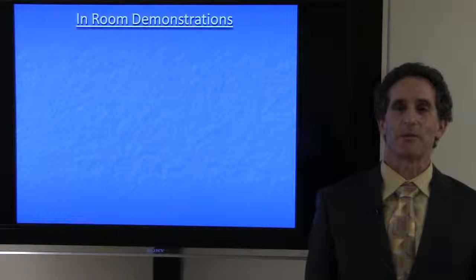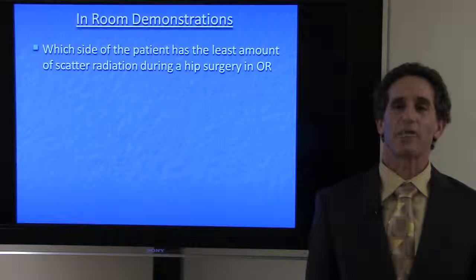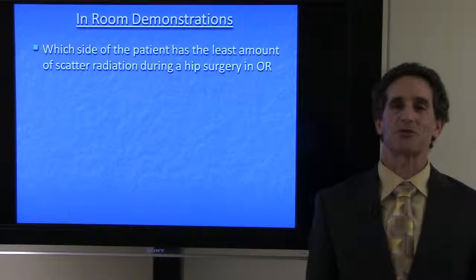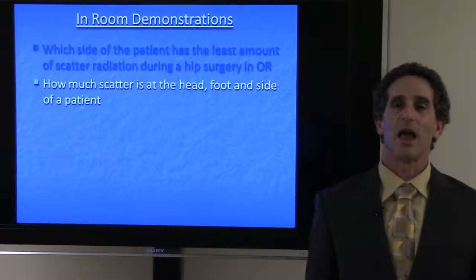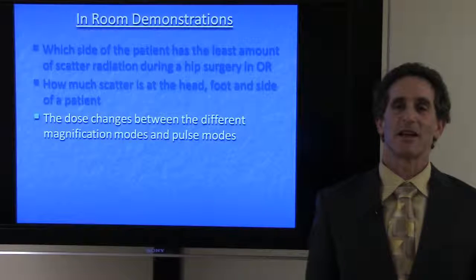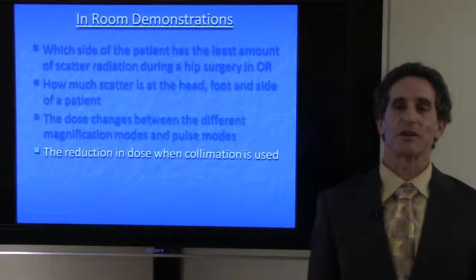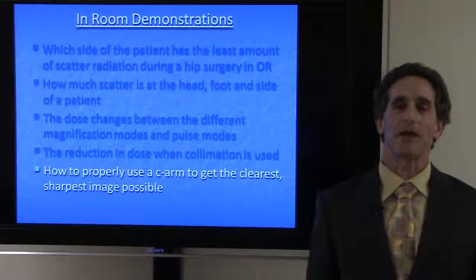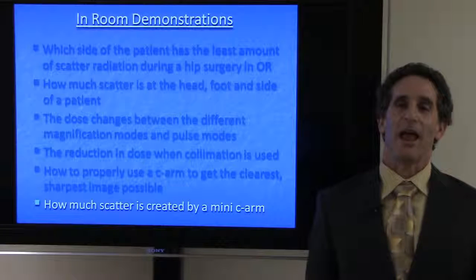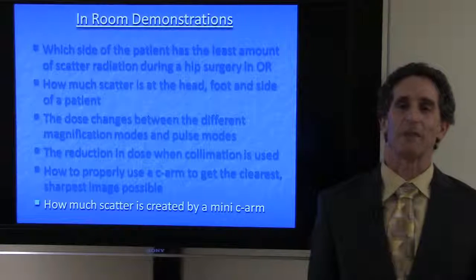Some of the in-room demonstrations include which side of the patient has the least amount of scatter radiation during a hip surgery in the OR, how much scatter is at the head, foot, and side of a patient, the dose changes between the different mag modes and pulse modes, the reduction in dose when collimation is used, how to properly use a C-arm to get the clearest and sharpest image possible, and how much scatter is created by a mini C-arm.